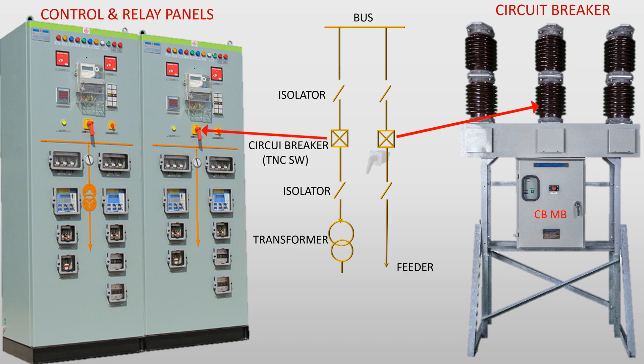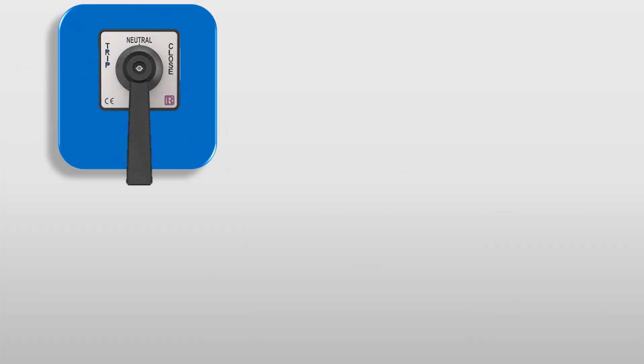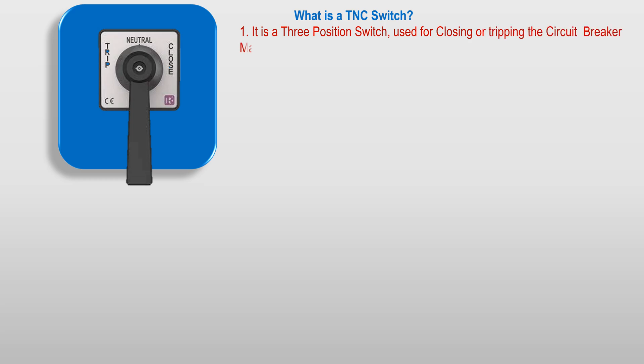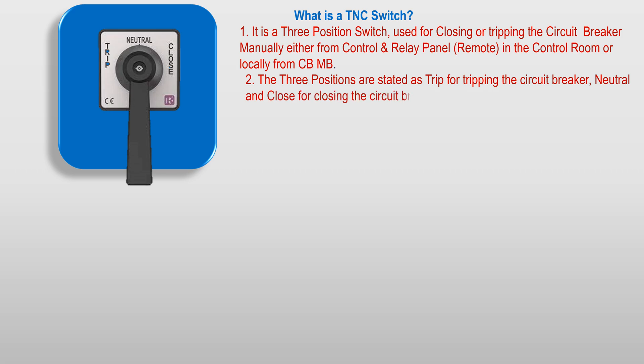A TNC — trip neutral closed switch — which is incorporated with the control panel, can make the circuit breaker on and off manually. The TNC switch is a three-position switch used for closing or tripping the circuit breaker manually, either from the control and relay panel remotely in the control room or locally from the circuit breaker mechanism box. The three positions are: trip for tripping the circuit breaker, neutral, and close for closing the circuit breaker.